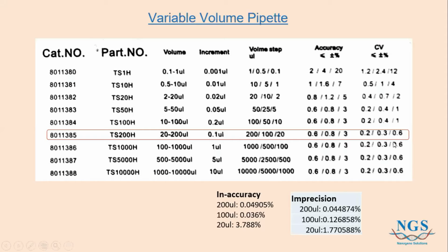It means that probably when you were testing your liquid, when you're measuring your weight, something might have been wrong, or maybe the technique has been wrong, some human error or anything. Yeah, your eye level might be wrong. So that is something that you cannot really change. You can just acknowledge it and maybe try not to make the same mistakes again. But when we're talking about inaccuracy, when it's out of range, it is something that you should look into if you want to calibrate your pipette. So let's talk about calibrating your pipette.